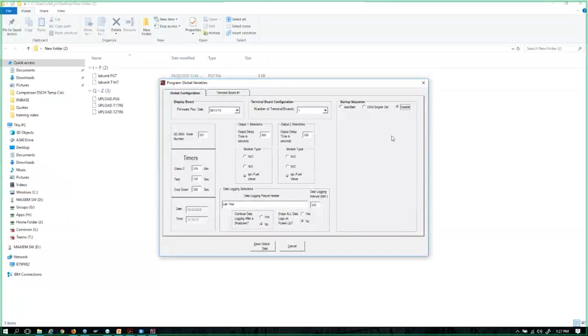Disable is commonly used if somebody has an older annunciator system, such as a DD40 or a DD20, and they simply want to upgrade to a DE-3000, but they don't really want to change any controls out on the unit. They can simply push reset on the keypad of the DE-3000, or trigger a remote reset, and it will simply turn on outputs 1 and 2 instantly. But in this middle section we have an option for when we turn off these 2 outputs. So let's use an example. Let's say we're using output 1 to control the fuel valve, and output 2 to control the ignition or the G lead.